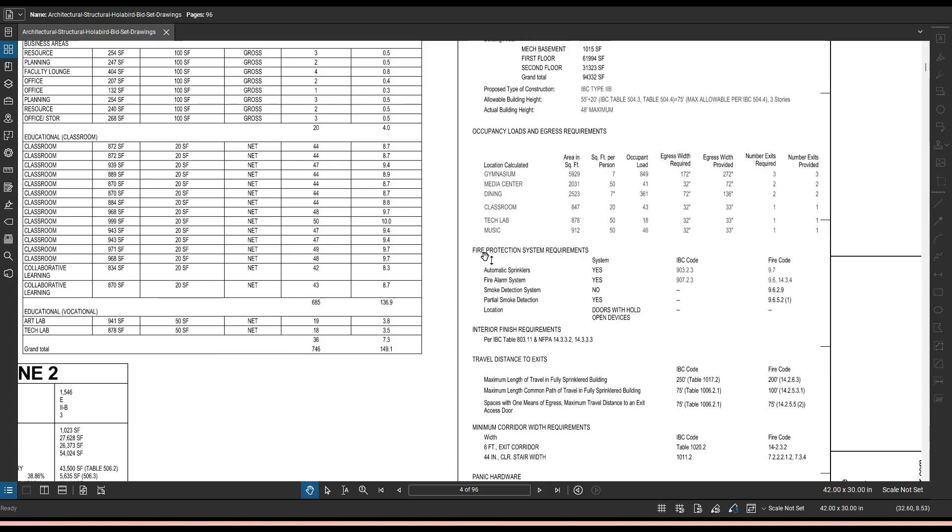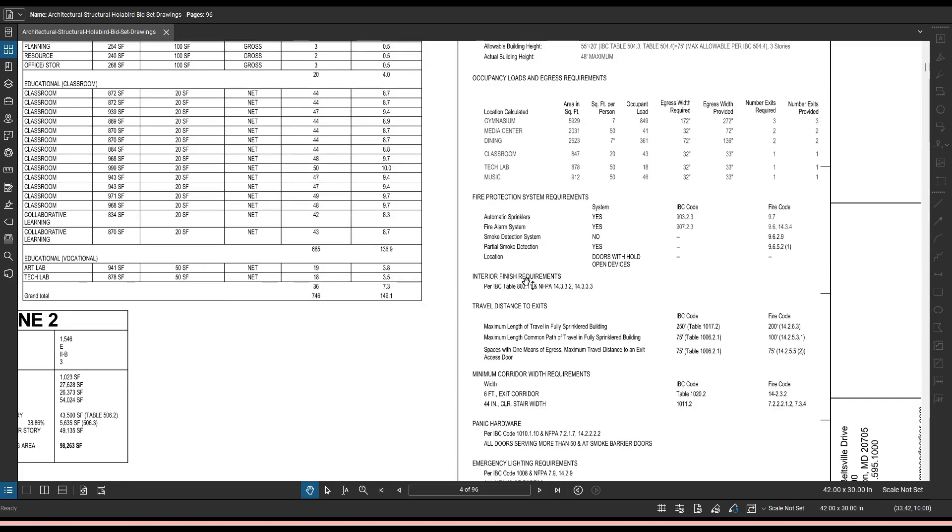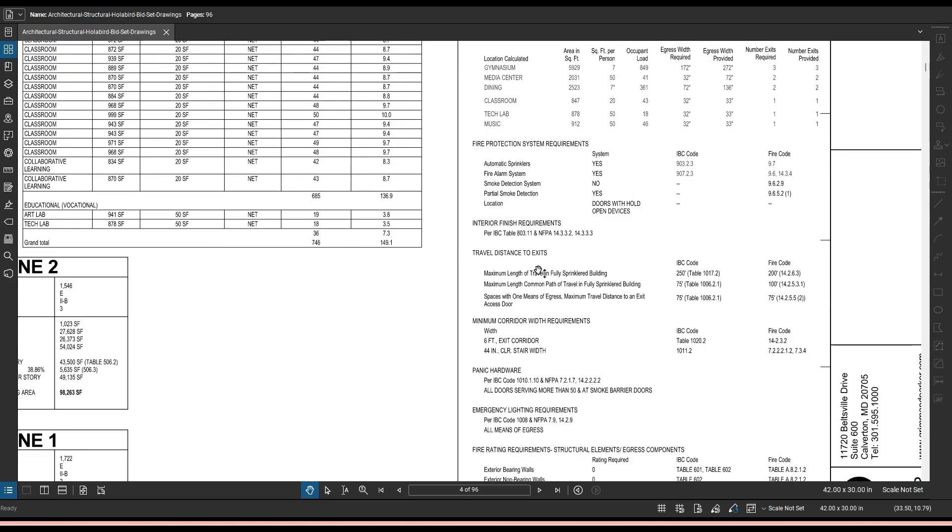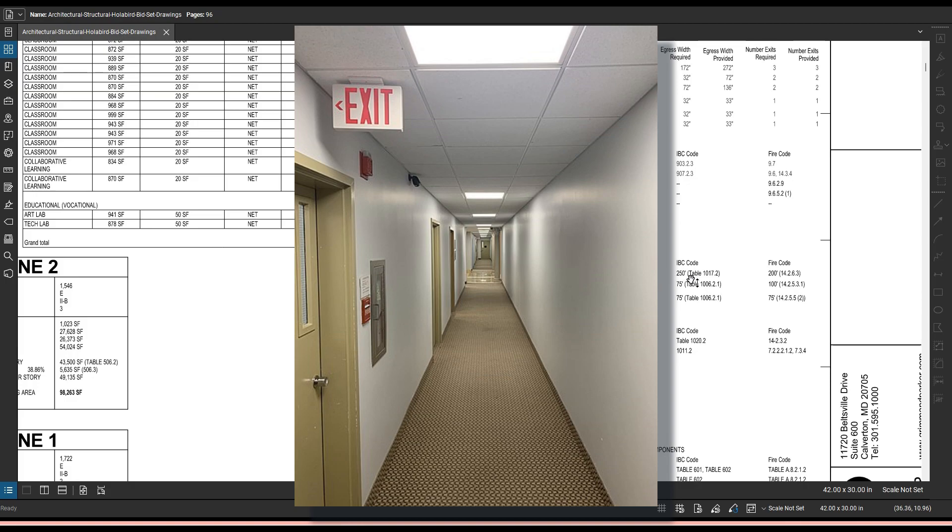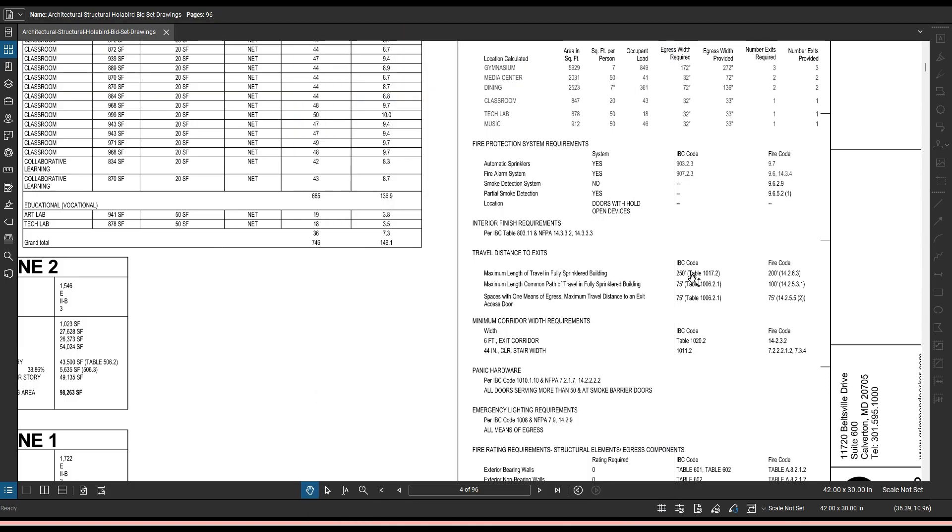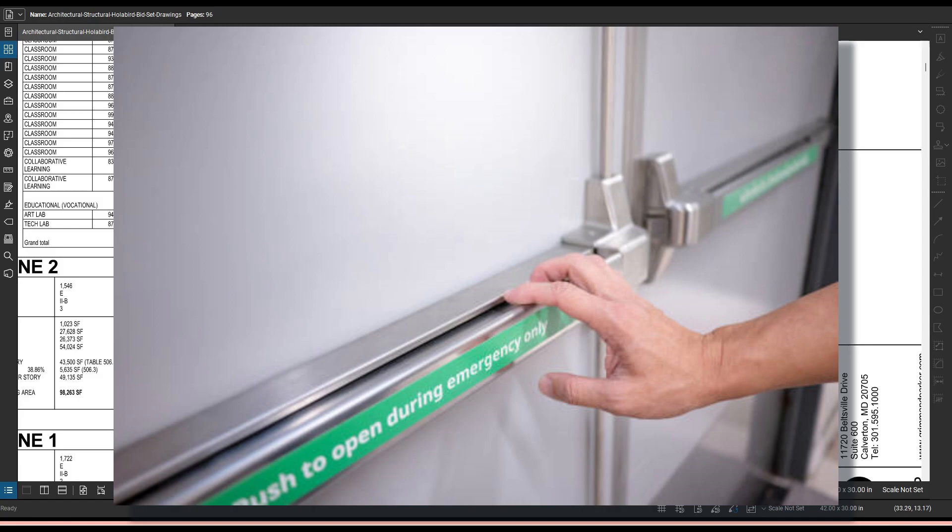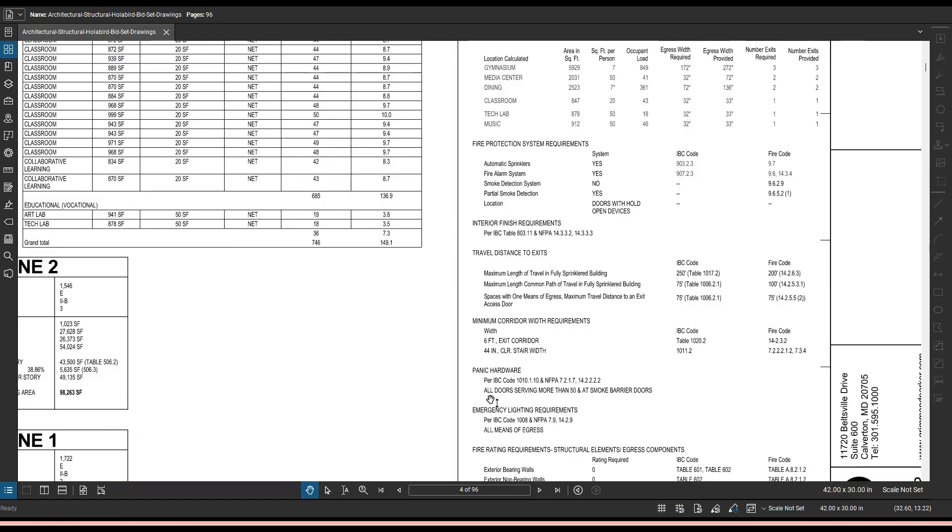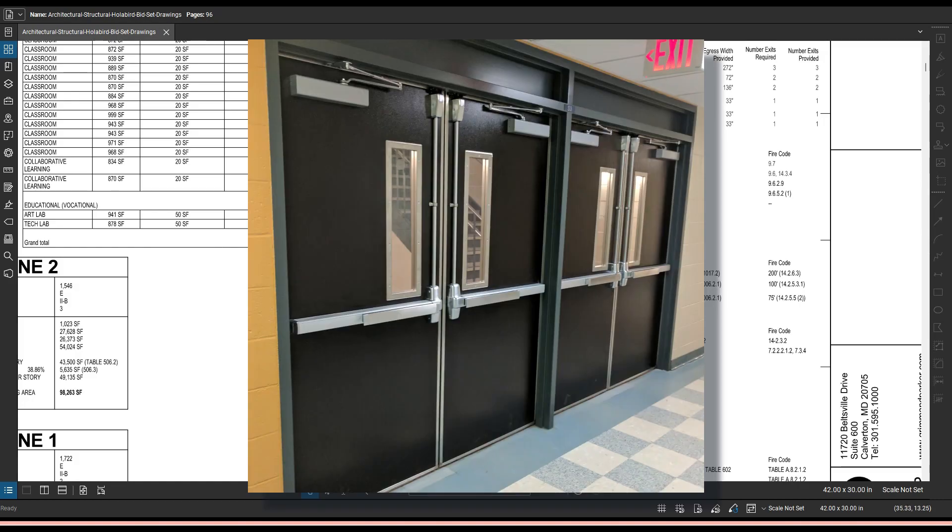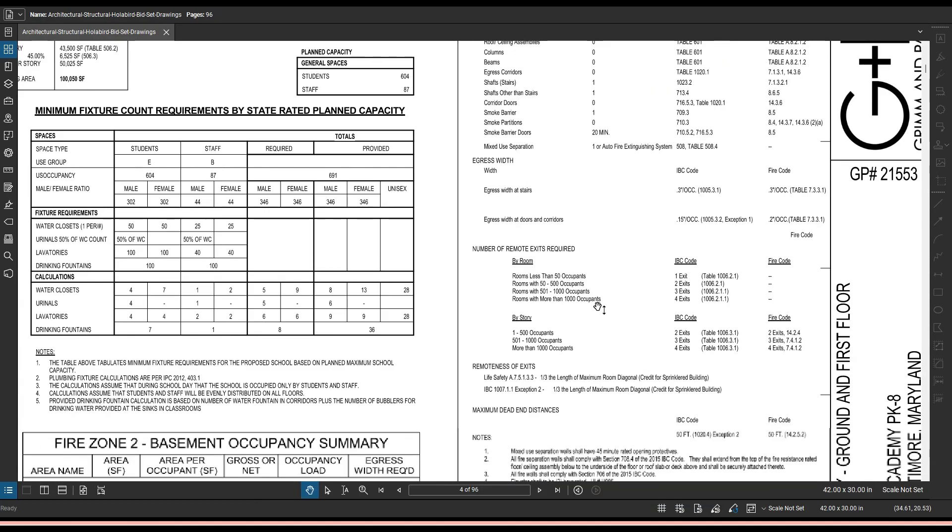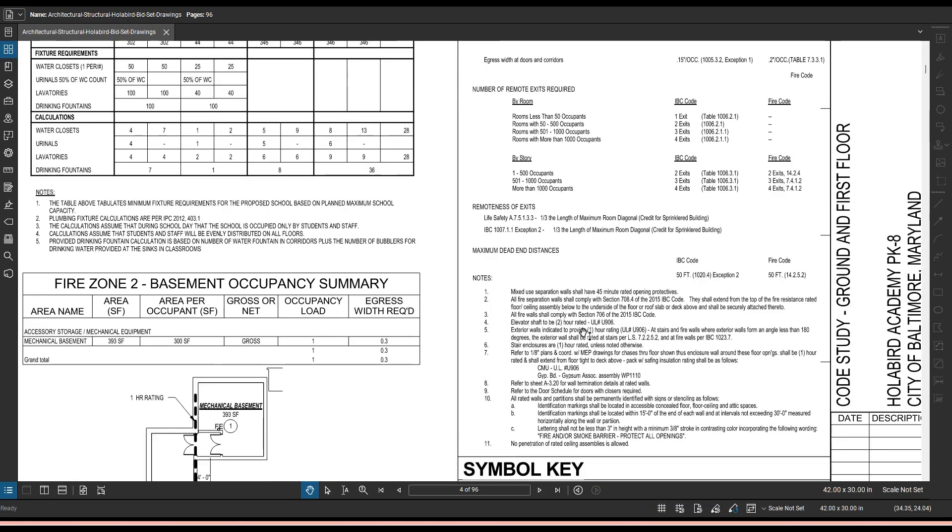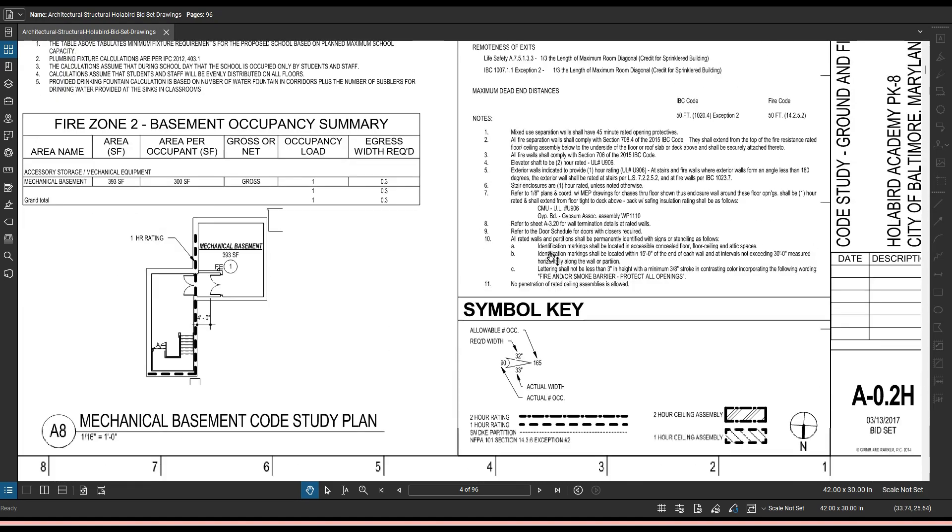So it's the same as you go through and you look at the fire protection system requirements, the interior finish requirements. All of these are listing out codes and tables for this building to adhere to in order to be within the code. So it even talks about travel distance to exits. I'll show you that in a second, but that basically means how far does someone have to travel if they're in a particular corner of the building that's furthest away from an exit. Panic hardware is like when you're exiting a building and you have to push to exit. In this building it's telling you that all doors serving more than 50 people and smoke barrier doors have to have that panic hardware. We're not going to go through all of these, but you can kind of do your own reading and get the point.